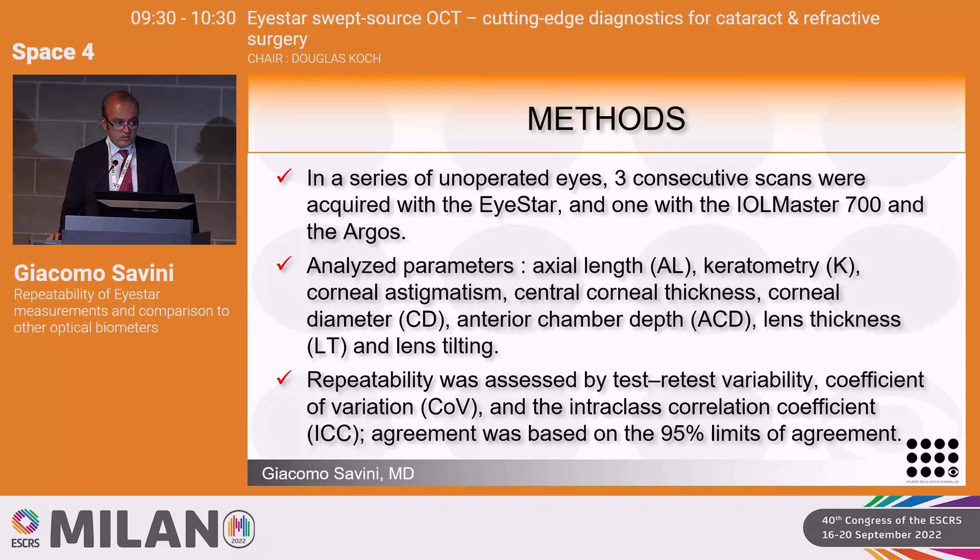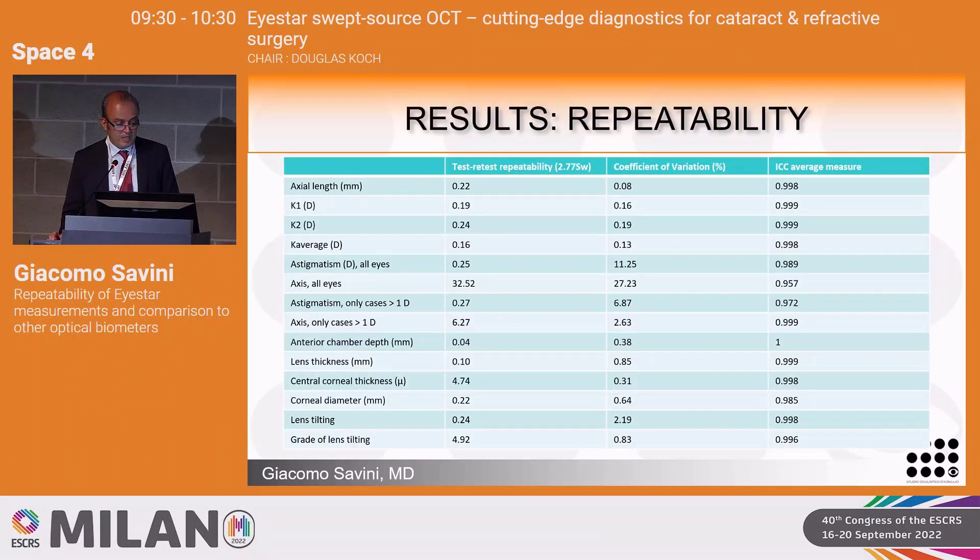To assess repeatability of the three EyeStar measurements, we used test-retest variability, coefficient of variation, and intraclass correlation coefficient. Agreement between each pair of biometers was based on the 95% limits of agreement according to Bland and Altman. Looking at the coefficient of variation — the most important column — all measurements excluding astigmatism have a coefficient of variation in most cases below 1%, so variability less than 1%.